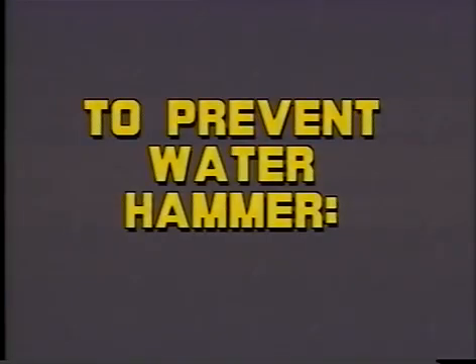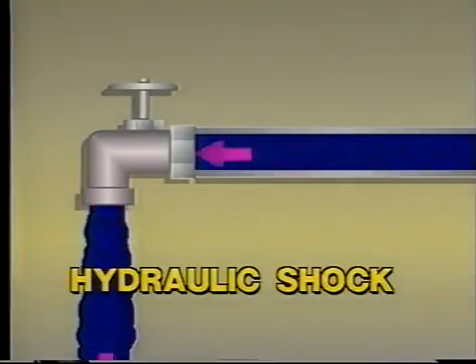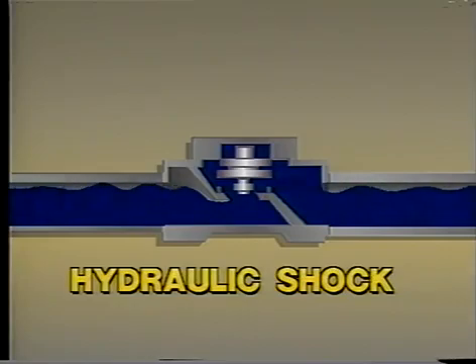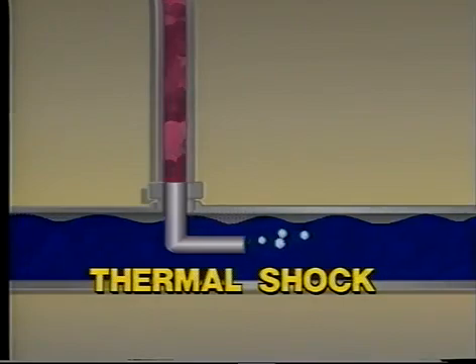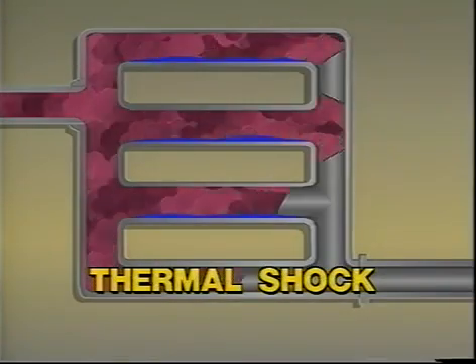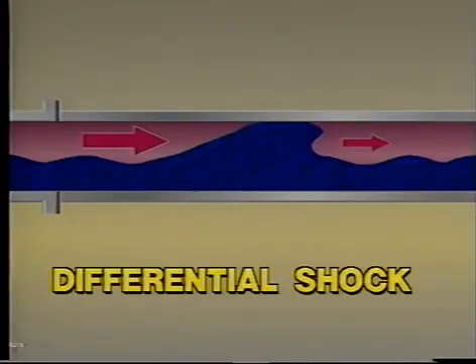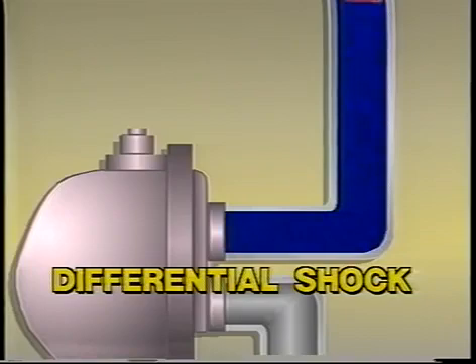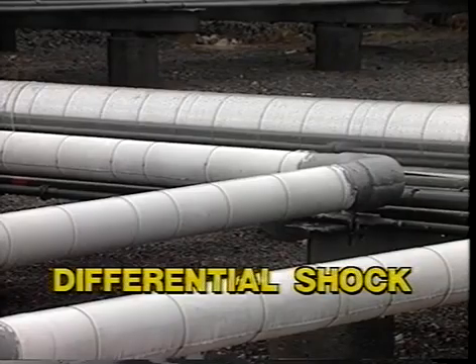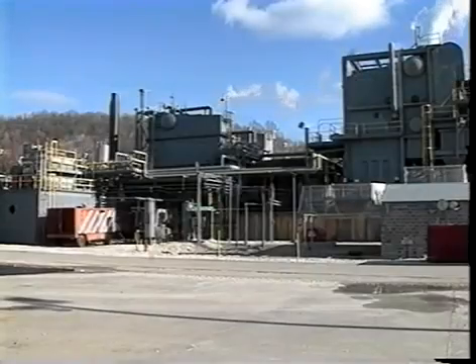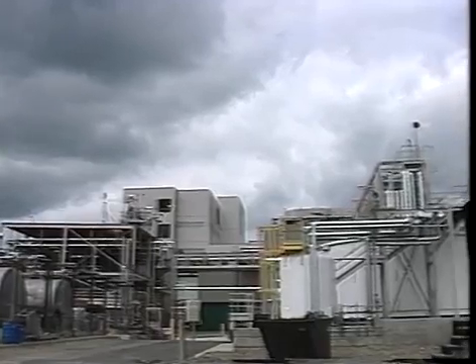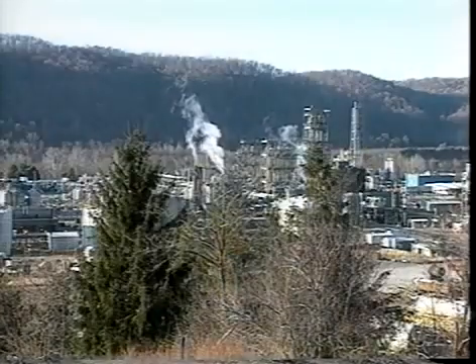Careful attention to these few guidelines will prevent most water hammer. Prevent the sudden stopping of water in pipelines by closing manual valves slowly, and by installing spring-loaded, center-guided, silent check valves where appropriate. Prevent thermal shock by using a sparging tube wherever flash steam is discharged into condensate at a lower temperature, and by ensuring that heat exchanger tubes are filled from one end. Prevent differential shock in bi-phase systems by providing return lines that are properly pitched and of adequate size. Avoid draining equipment with long lines to the trap, and insulate condensate lines whenever necessary. Following these guidelines for the proper design and operation of your system will minimize the likelihood of the shocks that cause water hammer. This, in turn, will greatly reduce the likelihood of damage to your system, to your product, and to your personnel.